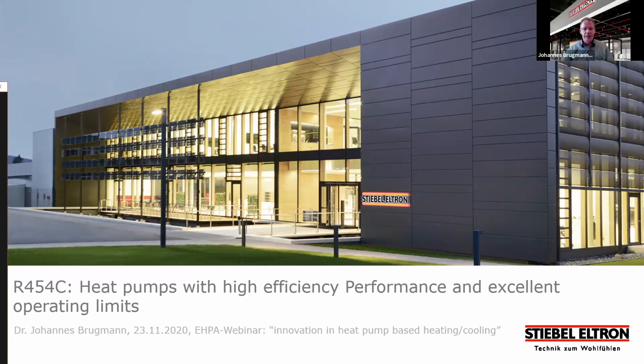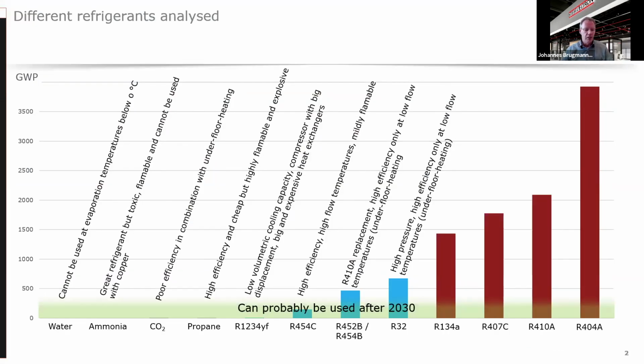We decided in 2016 to start a new development, and one of the main goals was the development of the heat pump with a new refrigerant that is in line with the objectives of the F-gas directive and can be used also after 2030. For that reason, we investigated, of course, the probable refrigerants that can be used, and you can see the common refrigerants that are used today, and we looked at the refrigerants that are below R32, because that is one of the refrigerants that is below 750, that is mentioned in the F-gas directive.